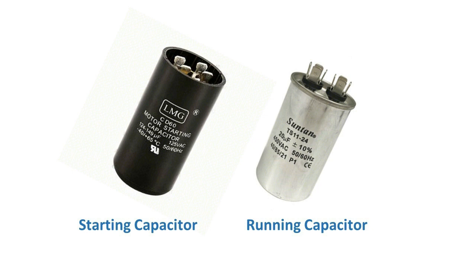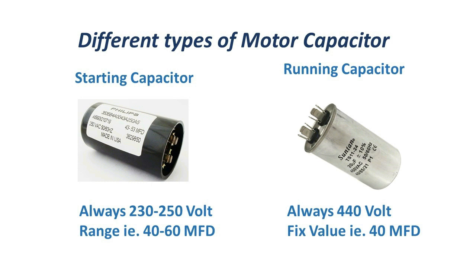Normally we use starting capacitors and running capacitors with induction motors. The value of a capacitor is measured in microfarad, picofarad, and nanofarad. Starting capacitors have values in ranges like 30-40, 40-60, 60-80, 80-100 microfarad, and are always rated at 230 to 250 volts AC.